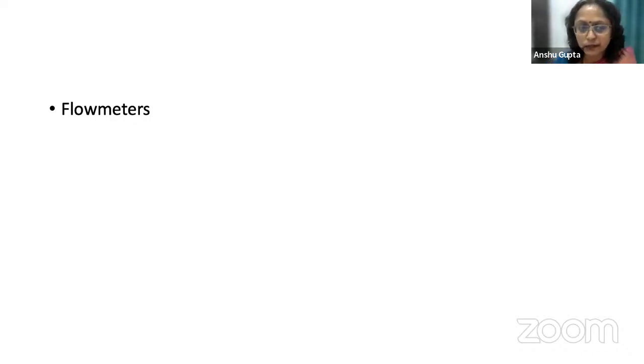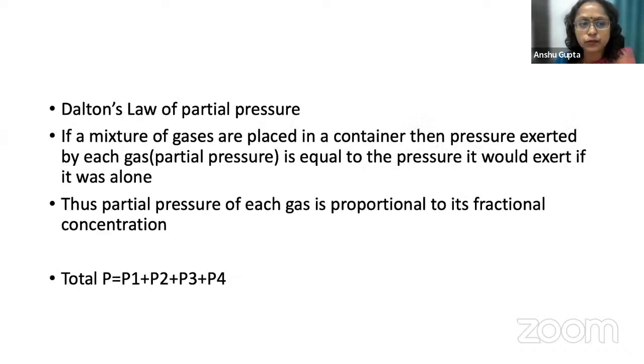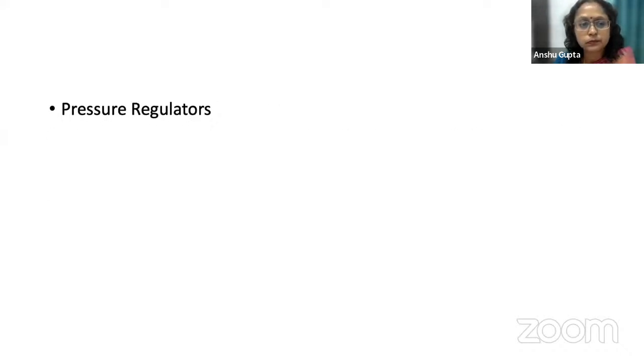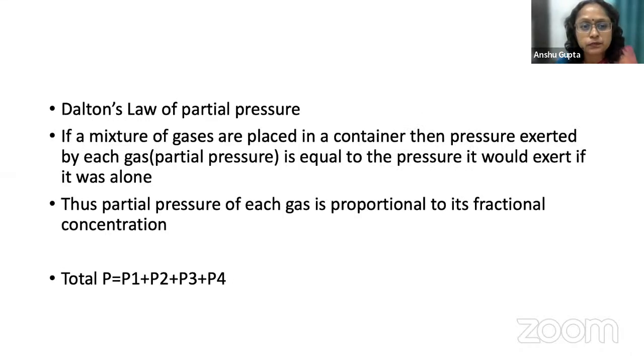And similarly, pressure regulators work on the principle that force is equal to pressure into area. So when the cylinders have high pressure, relief valves and pressure regulators decrease the pressure. The high pressure acts on a small area, and in the later part the area is increased, so pressure is decreased. This is the main principle.